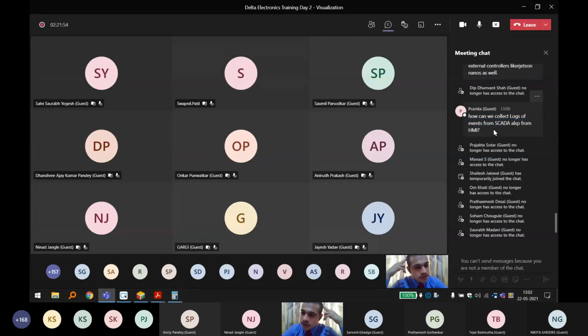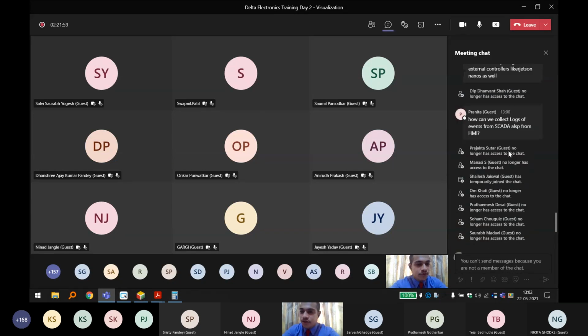Can we collect logs of events from SCADA also from HMI? Yes, you can, the SCADA will have to be connected to the HMI. SCADA is extensively used in the pharmaceutical industry, which is very strict about data collection, data logging, and report generation. A report is generated after each shift and it has to be in the correct format, so you definitely can collect logs of data.